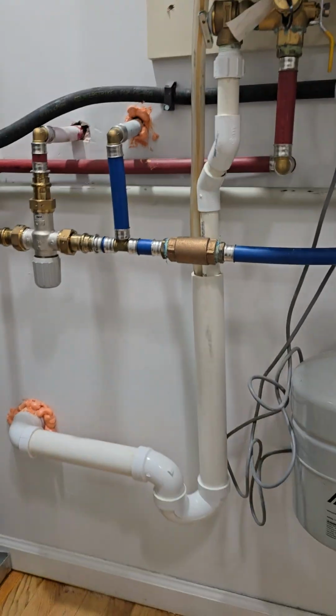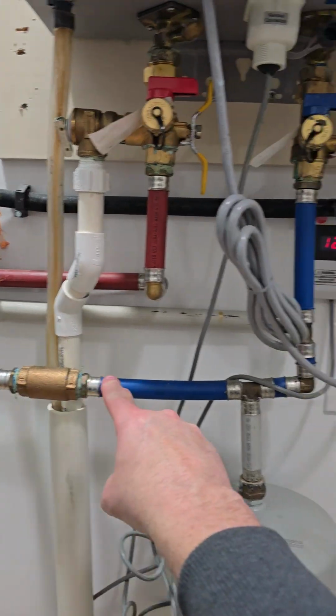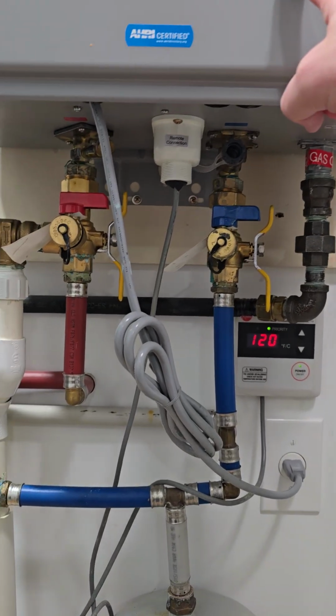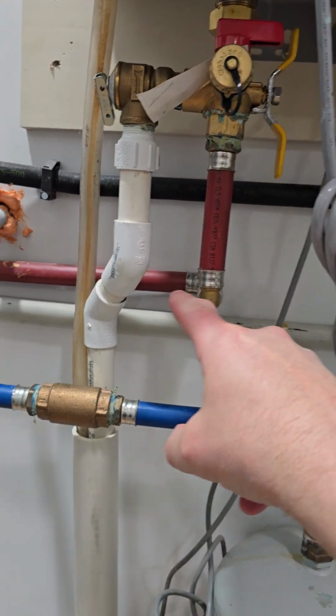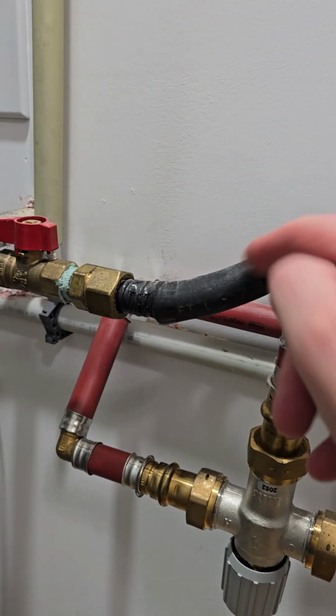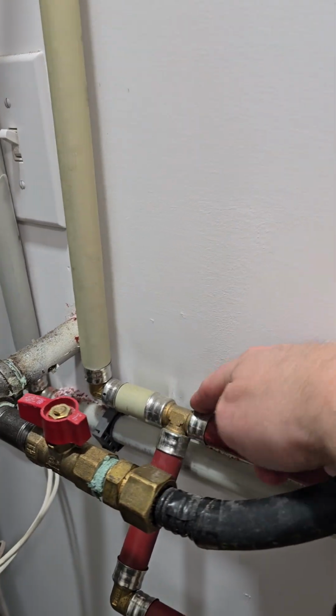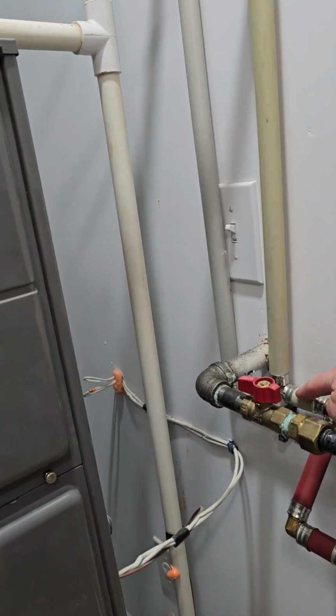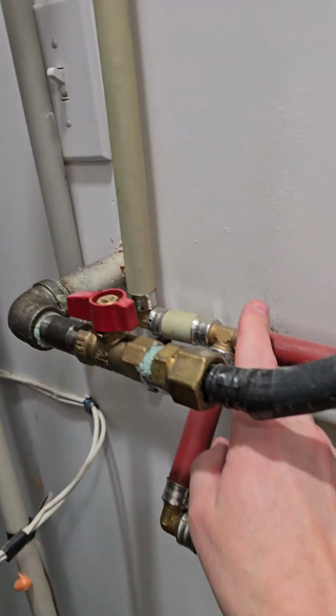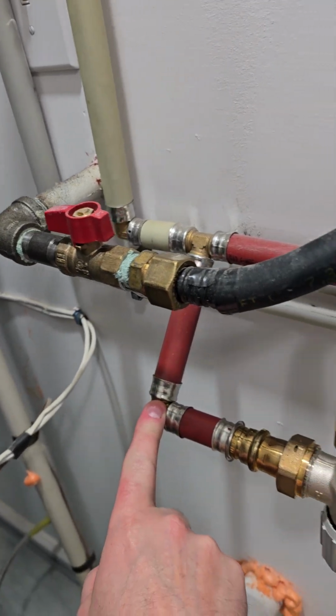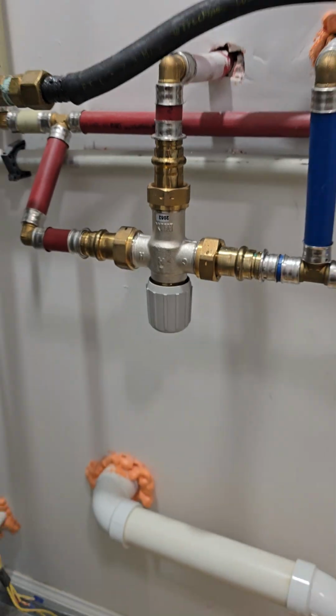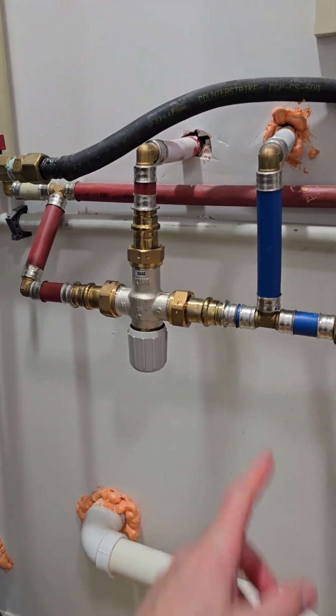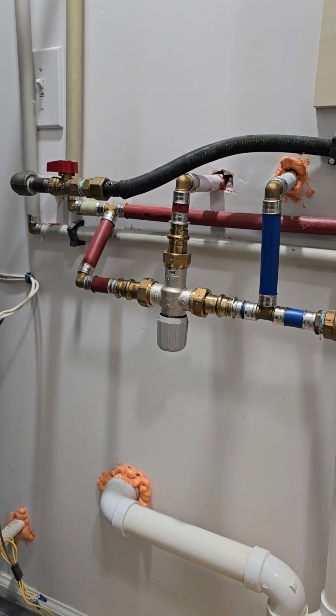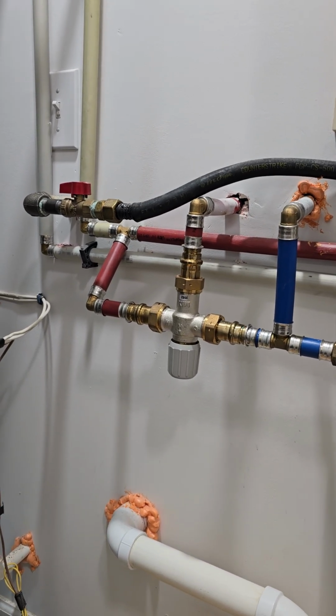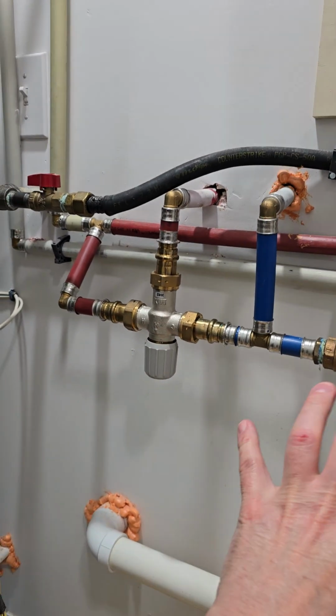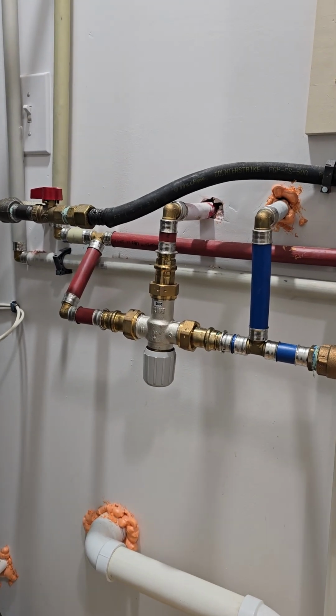Briefly, the way that works: cold water comes in, gets heated up by the heat exchanger, comes out here, goes along this red pipe. Let me know if you're bored yet. At this T, the water can go into your heat exchanger, or it comes down here into what they call a tempering valve, which mixes with cold water. The idea is you've got 140 degree water that you don't want going to the rest of the house for obvious reasons, so this tempering valve mixes with cold water to get you the temperature you want at the outlet.